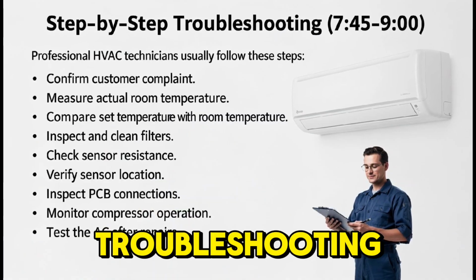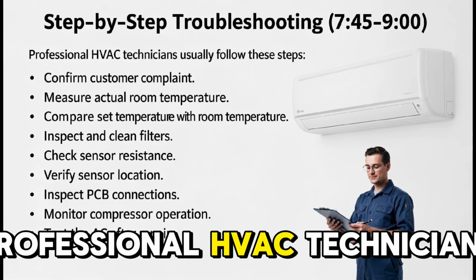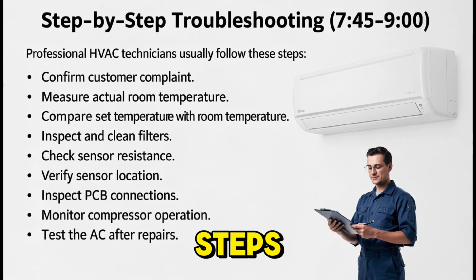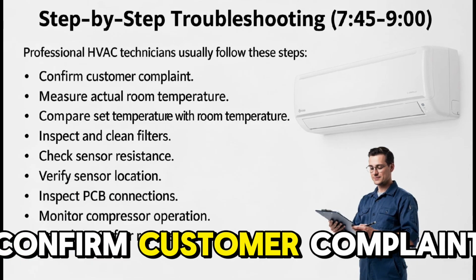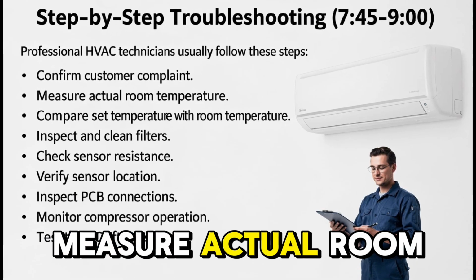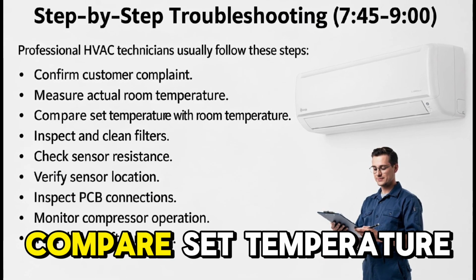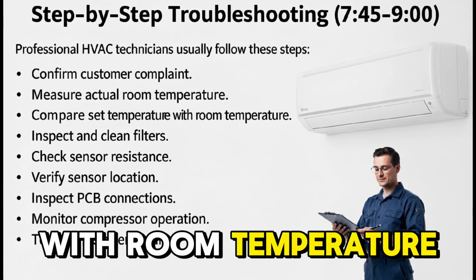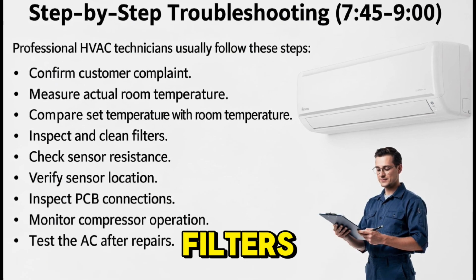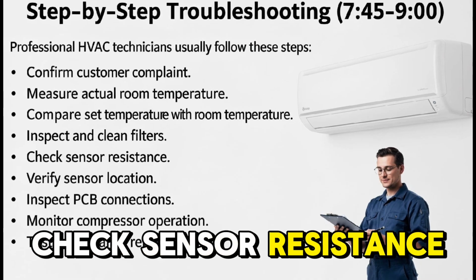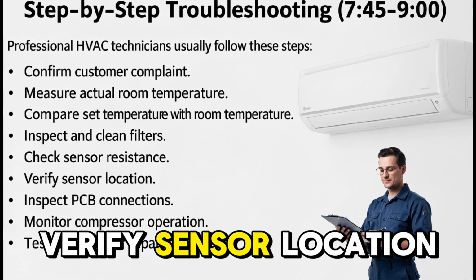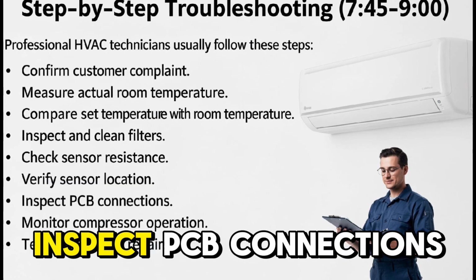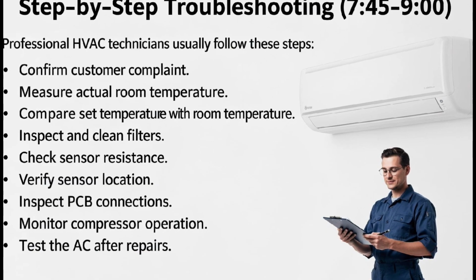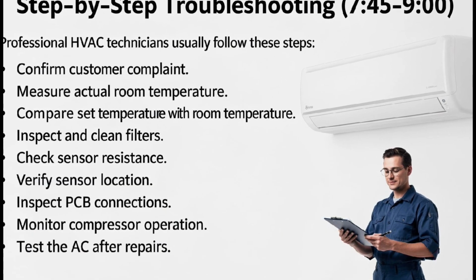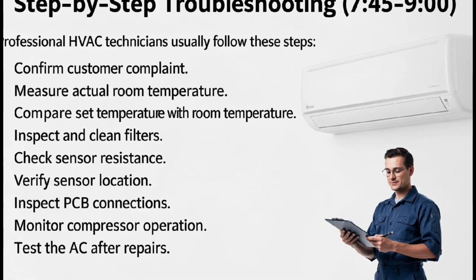Step-by-step troubleshooting. Professional HVAC technicians usually follow these steps. Confirm customer complaint. Measure actual room temperature. Compare set temperature with room temperature. Inspect and clean filters. Check sensor resistance. Verify sensor location. Inspect PCB connections. Monitor compressor operation. Check refrigerant system. Test the AC after repairs.